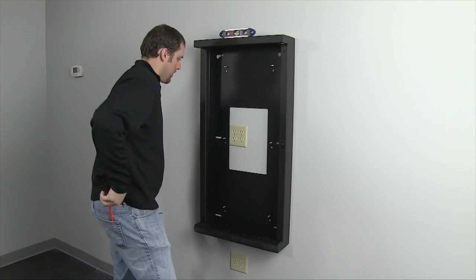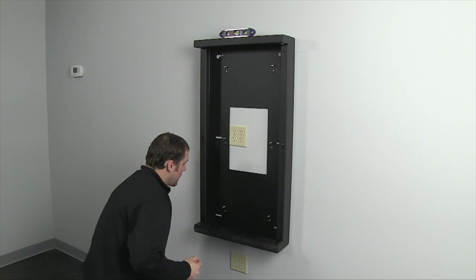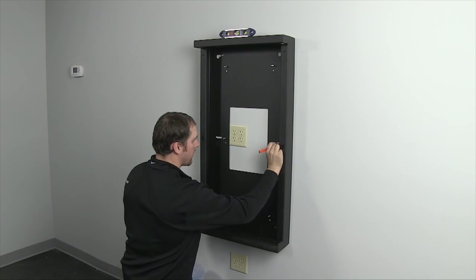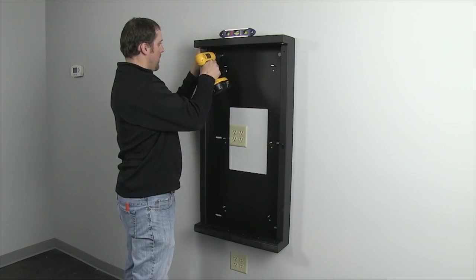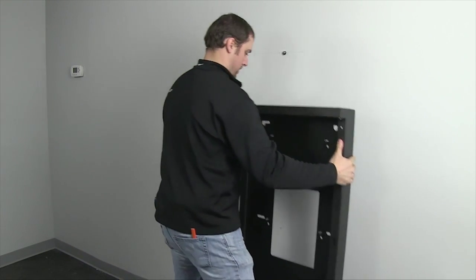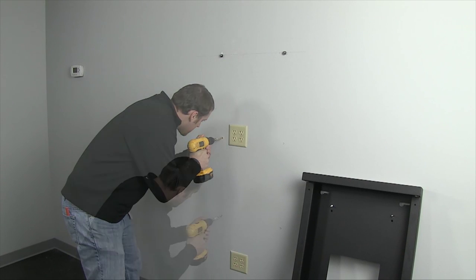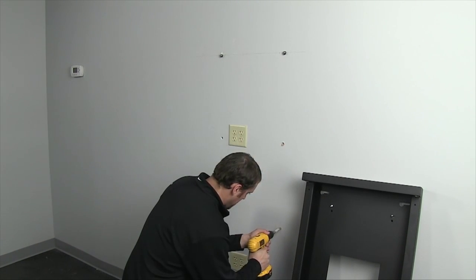Now mark the remaining mounting points within the rear section of the rack. Because the pilot holes for the anchors are larger than the slot in the rear rack section, the rack must be removed. Loosen the upper two mounting screws and lift the rear rack section from the wall. Drill the pilot holes at each previously marked location and then insert the remaining steel stud anchors.